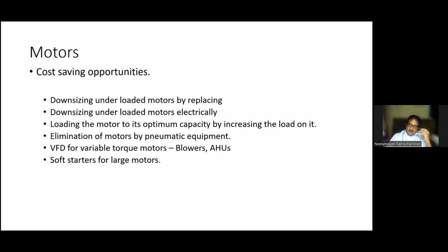On top of that, there are so many things. Downsizing underloaded motors by replacing them. Recently IE5 has come, so an IE3 or IE4 motor can be put in the place of the old motors. Downsizing of the underloaded motor electrically, I have a case study, I will let you know. And loading the motor to its optimum capacity by increasing the load on the motor, that also can be done.